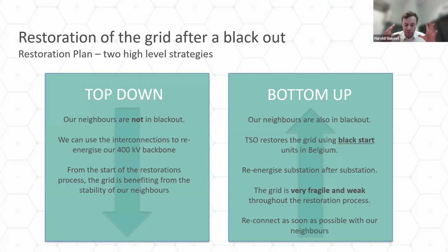And you can imagine like an oil spill that grows. So the grid would really be restored around those black start units and gradually, every substation, one after the other, would be re-energized. It is very important to remember that during a restoration, the grid is very weak and fragile, and any imbalance could cause it to trip back again. So that is certainly something that we need to keep in mind when we are restoring the grid.